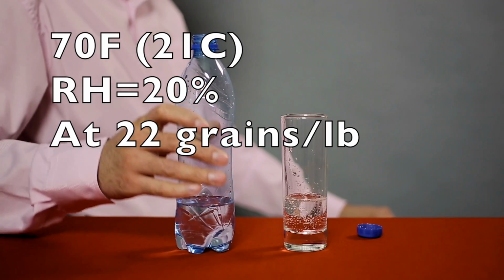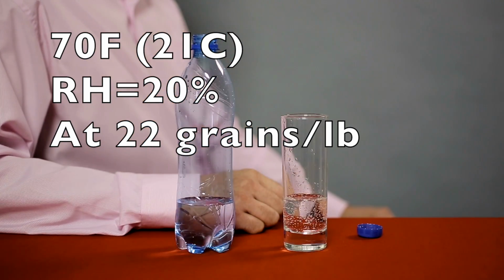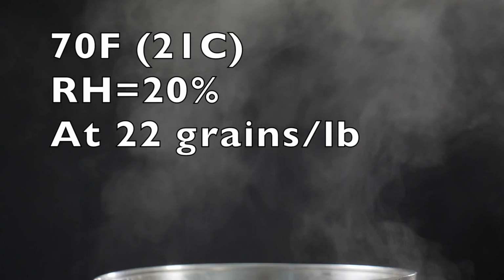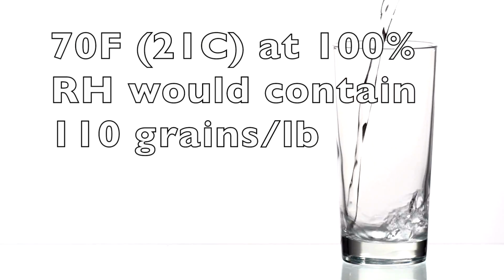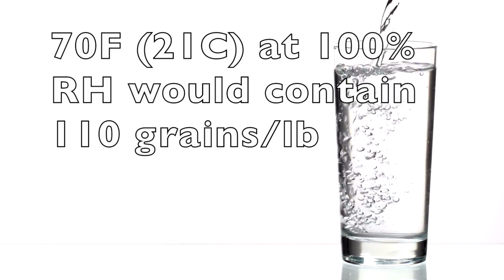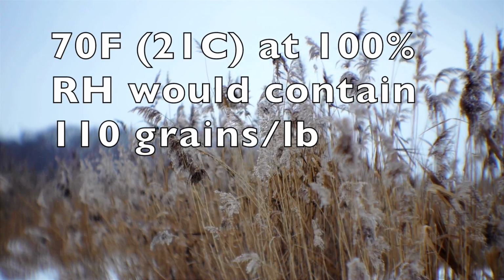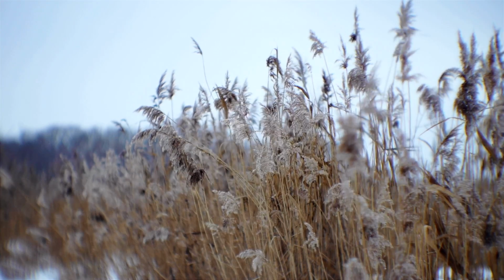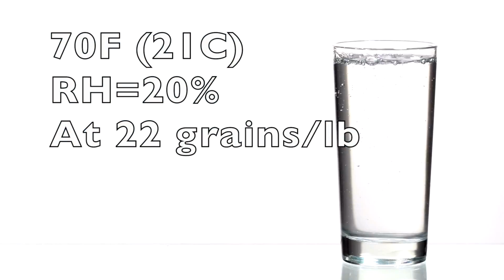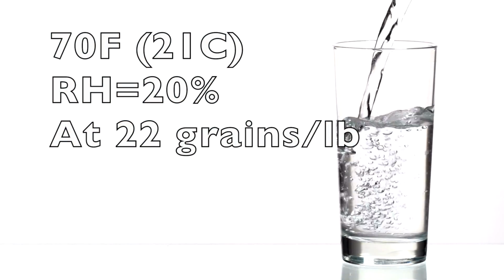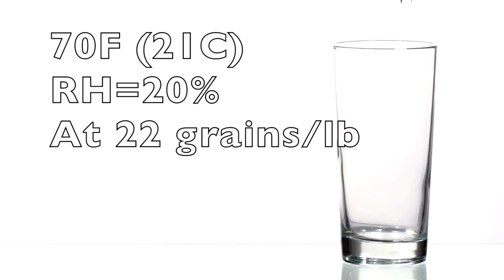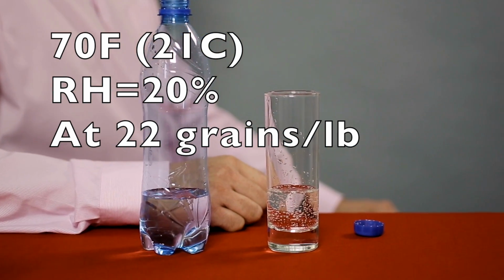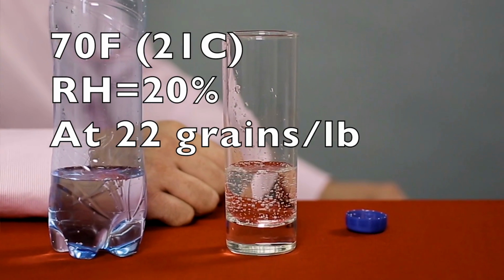Sounds pretty dry, right? In the warmer 70-degree air, there's a greater potential for water vapor through evaporation, around 110 grains per pound of potential. So when air with 22 grains per pound leaks inside and warms up to 70 degrees, it becomes apparent that it contains relatively little water vapor.